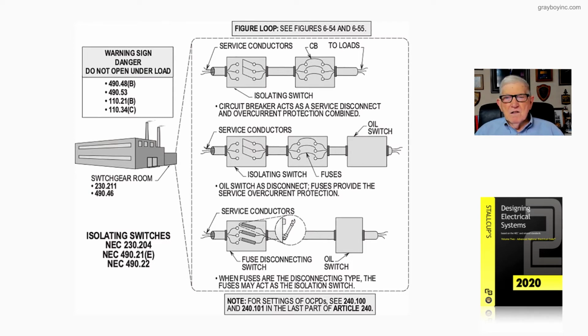Now, in the next illustration, you see the isolation switch, the disconnect there, just an isolation switch. Then you have an isolating switch ahead of the oil switch that you see there. And the oil switch is a disconnect. Fuses provide the service overcurrent protection. Now, a lot of the electricians did not like these oil switches because you couldn't see the make and break of an oil switch. They just didn't seem to like it.